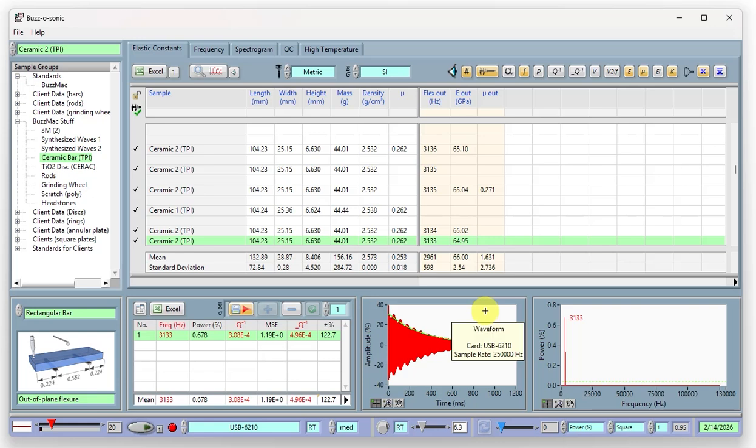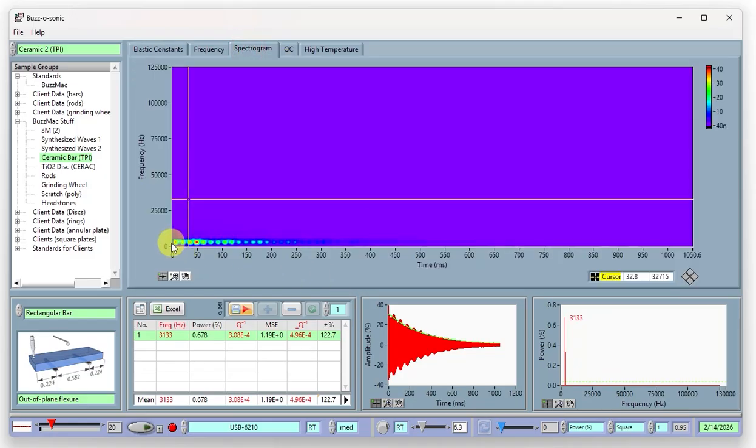Now, by using a xylophone mallet, the energy imparted into the sample is reduced to the lower frequencies. So the sample is going to vibrate at the lower frequencies because most of the energy is in the low frequency part of the spectrum. That means that we eliminate all the overtones by using this xylophone mallet rather than the standard impulse tool. And if you look at the spectrum now, you see we've basically only got one line here. The others are pretty much diminished. The overtones are fairly weak. We've got a very strong fundamental frequency.